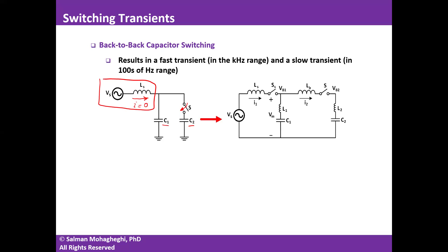On the right side, I have an equivalent circuit with source voltage V_S, source inductance L_S, and two capacitor banks. I've added stray inductances L1 and L2 in series, and L_B representing the inductance of the bus bar connecting C1 and C2. Because switching occurs at zero crossing of current, I1 is zero, so I can assume the left side is disconnected from the right side.